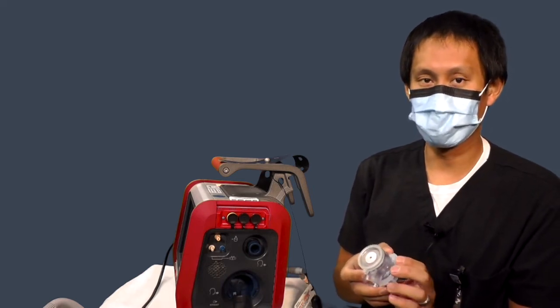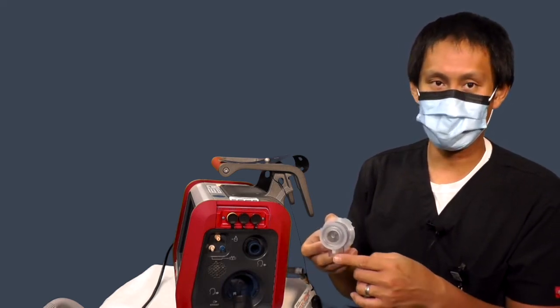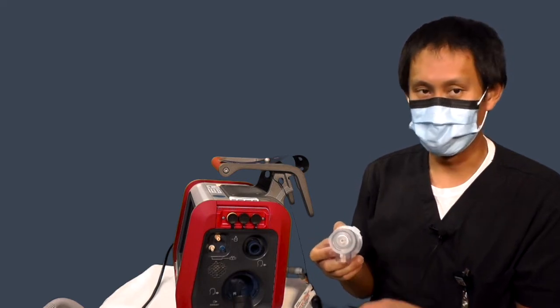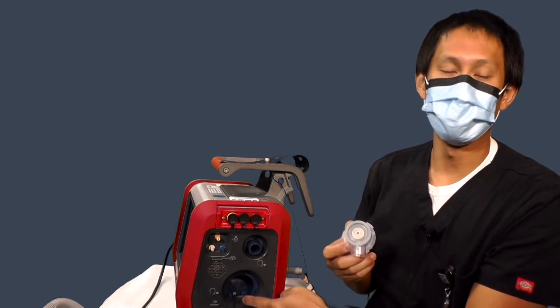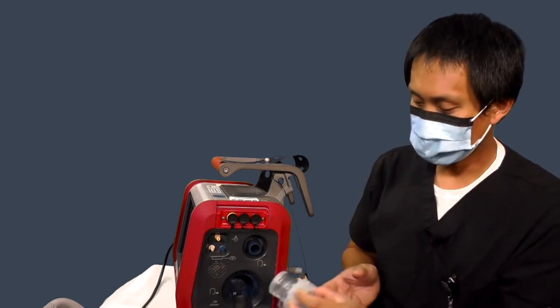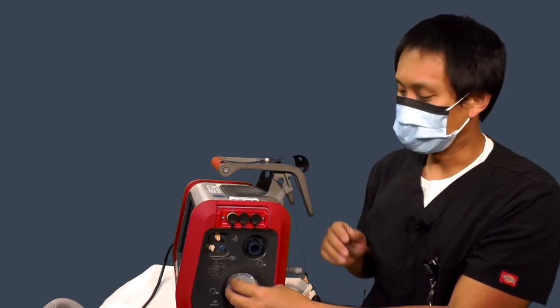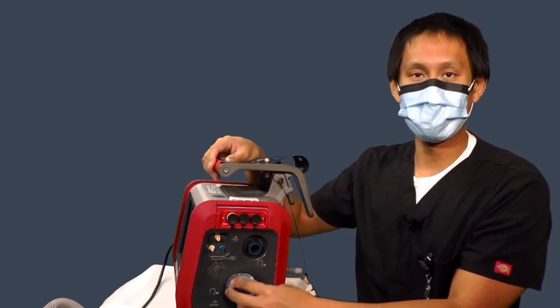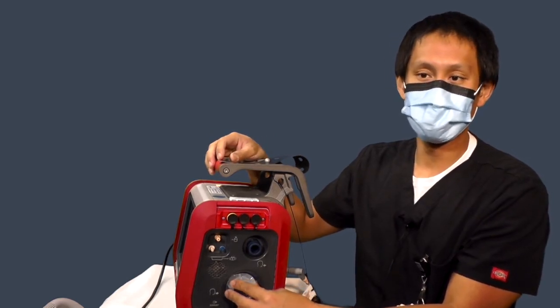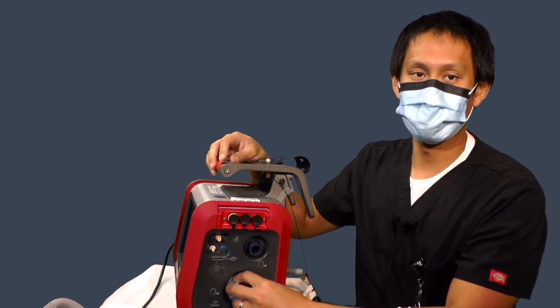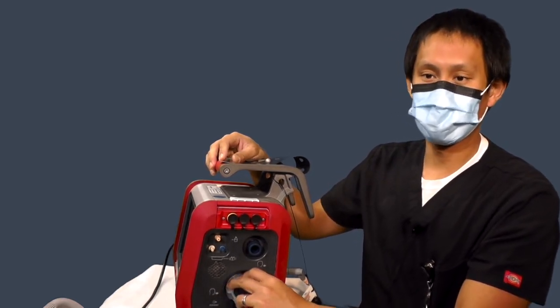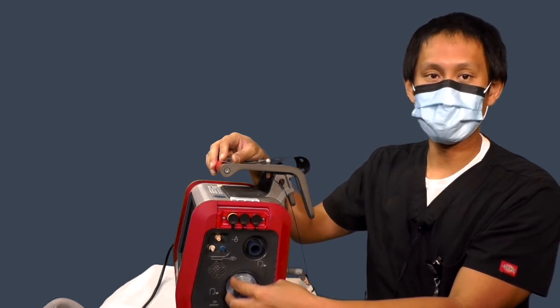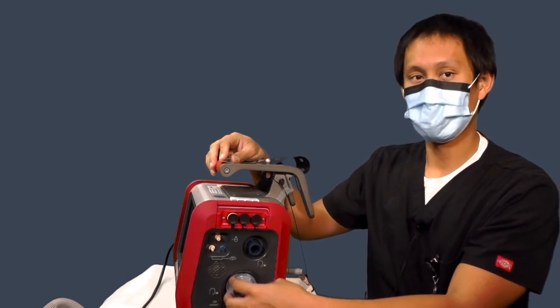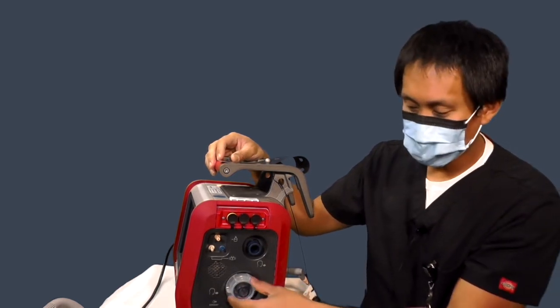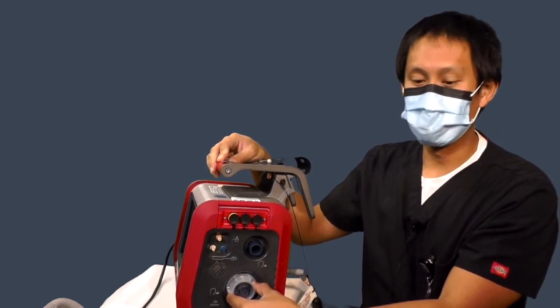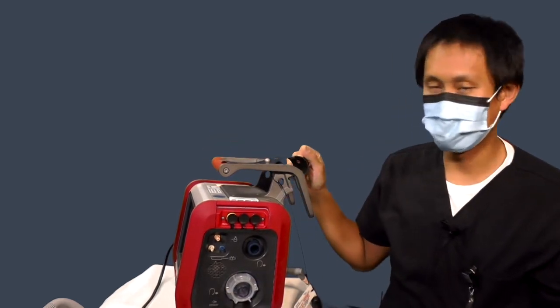Alright, so let's put this into the ventilator. As we mentioned, there's a notch down here at the very bottom of the expiratory valve. There's also a notch inside the ventilator itself. Line up that notch. As you get good at doing this, you can do it pretty much blind, just by feel. Once you put it in, find the notch. What you want to do is do a quarter turn, and you'll feel it click. Once you feel it click, or it doesn't turn any further, it is secured into the ventilator. And you can double check by trying to pull it out. If it doesn't come out, it's properly seated inside.